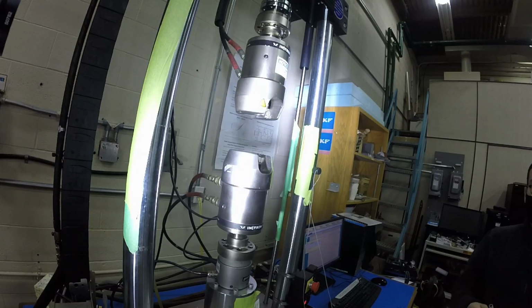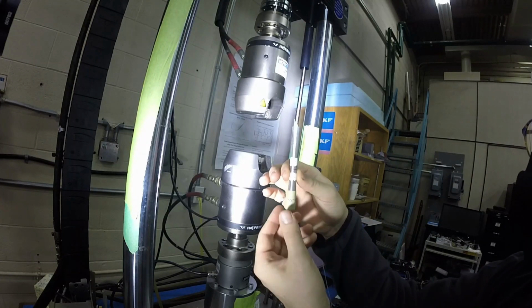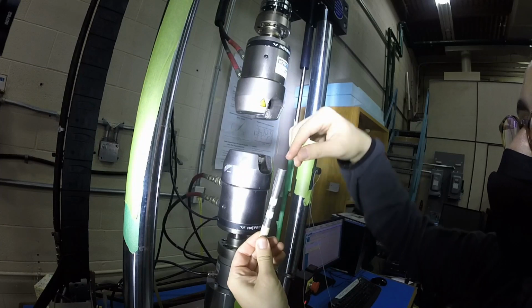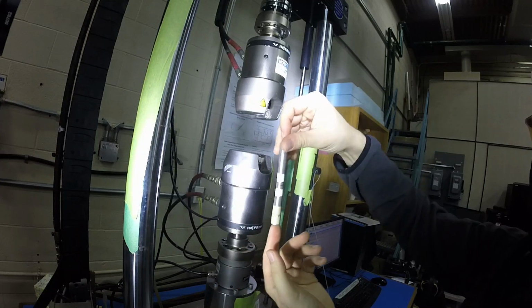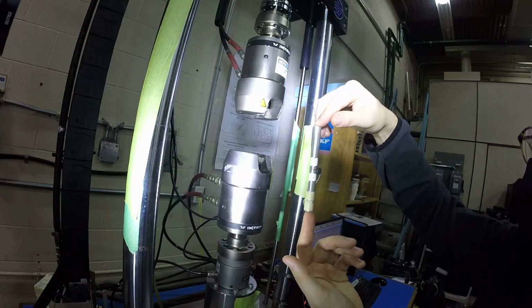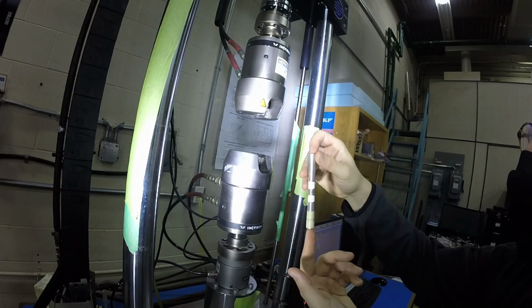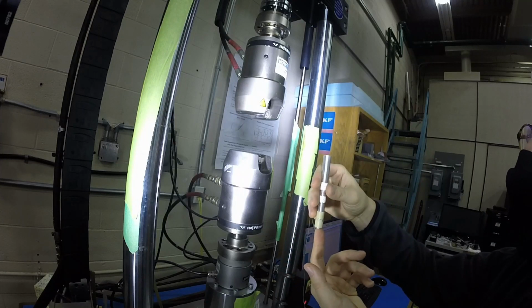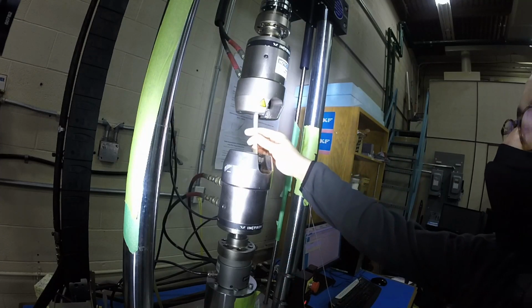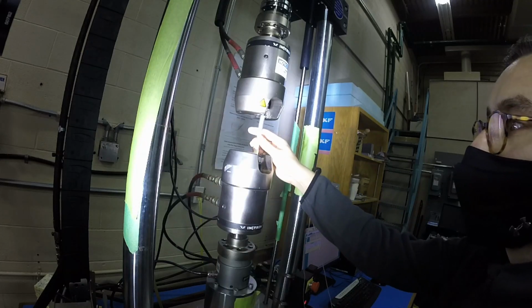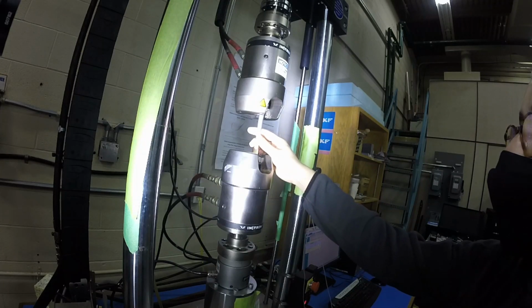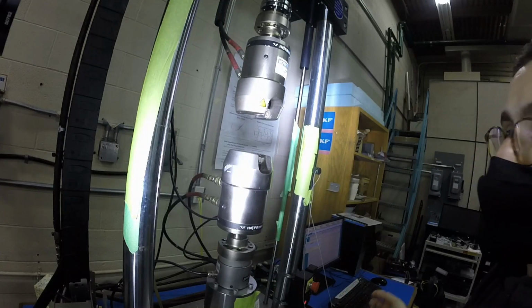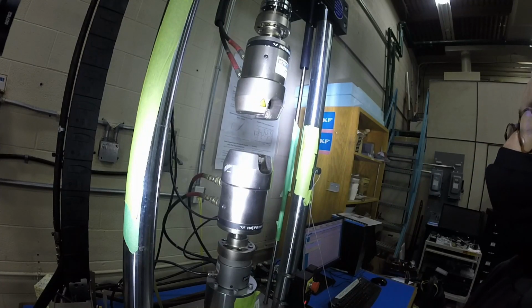So in order to prevent the sample from buckling under high gripping loads, there's specific plugs that you can use to actually get inserted into the ends of the sample, and especially for shorter samples, that's useful so that you have enough crosshead distance here to either use digital image correlation to measure the surface, or the extensometer to measure the strains that you're wanting.